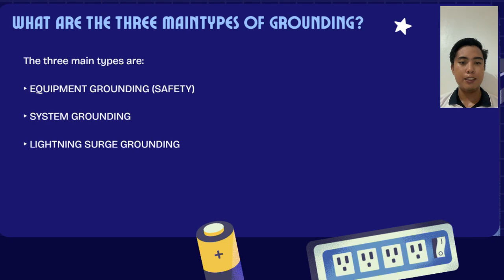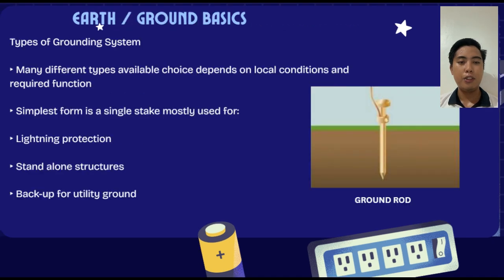So second is system grounding. It connects parts of the electrical system, usually the neutral, to the ground to stabilize voltage level and ensure proper operation of the system during normal and fault conditions. So the last is lightning surge grounding. It provides a direct path to the earth from high voltage surges caused by lightning, protecting buildings and electrical equipment from damage. Earth or ground basics. So there may be different types of grounding systems. The available choice depends on the local conditions and required function.